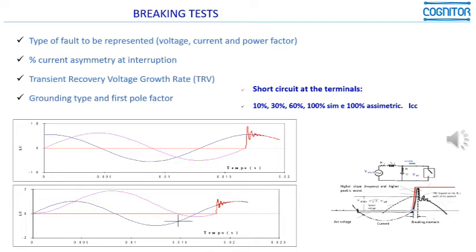There is also, as we see in the blue part on the right side of this slide, the simulation of short circuits at terminals at 10%, 30%, 60%, 100% of the short circuit currents. And you could ask me the following: okay, sir, why not do only the test at maximum short circuit current, let's say the 100% test?